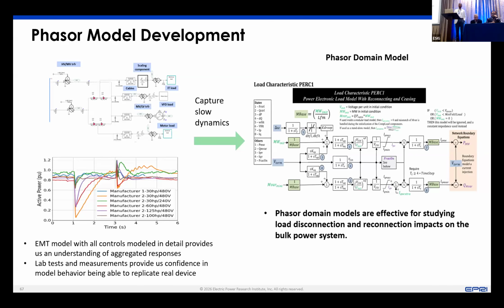We tested a bunch of power electronic equipment: EV chargers, variable speed drives, UPS systems and more. They give us unit-level ideas of what these devices do when you have different types of disturbances impressed on the terminals. That is one piece of the input. Then we also developed EMT models similar to what Shahil, Jane and Brett presented.